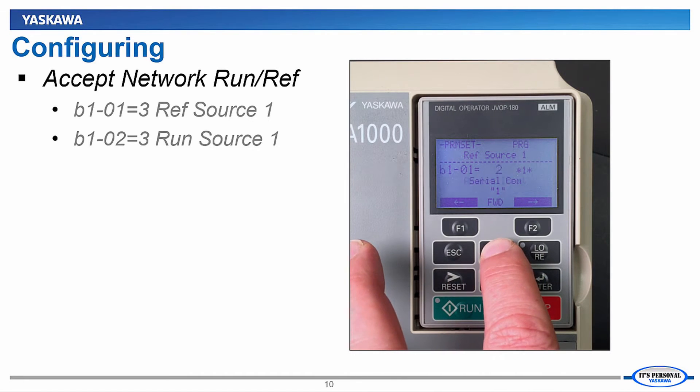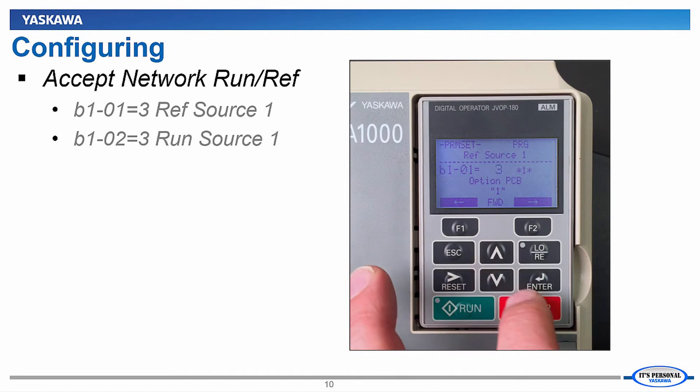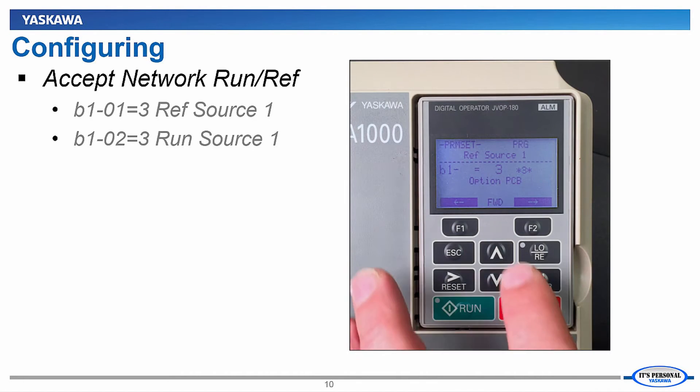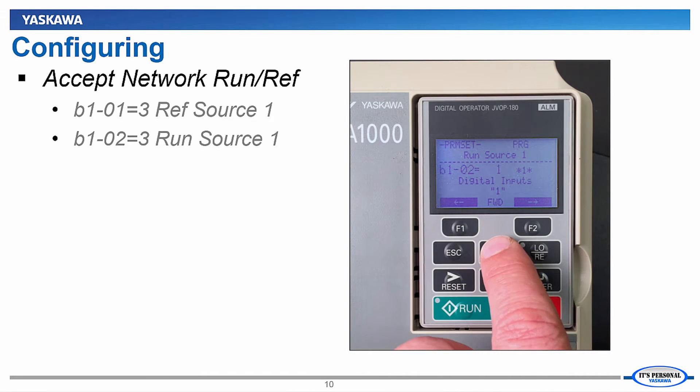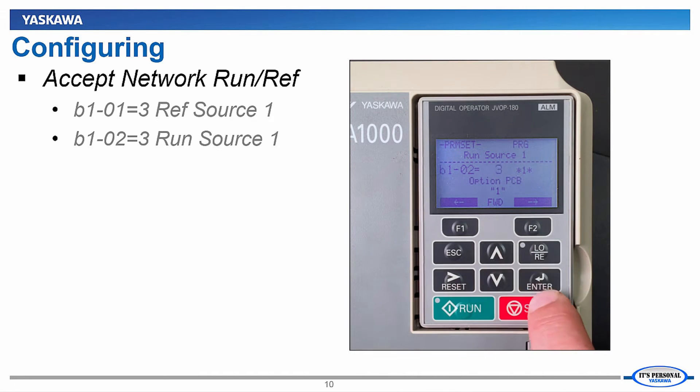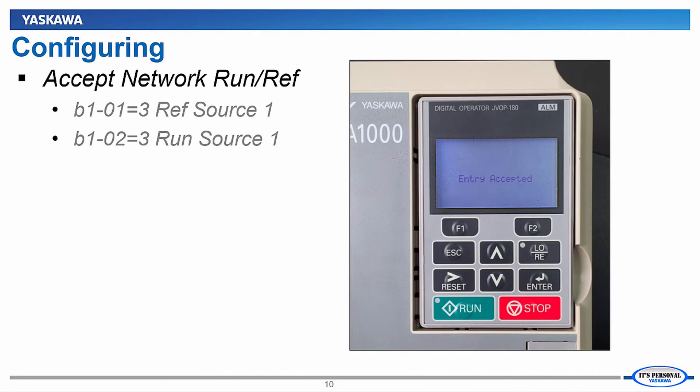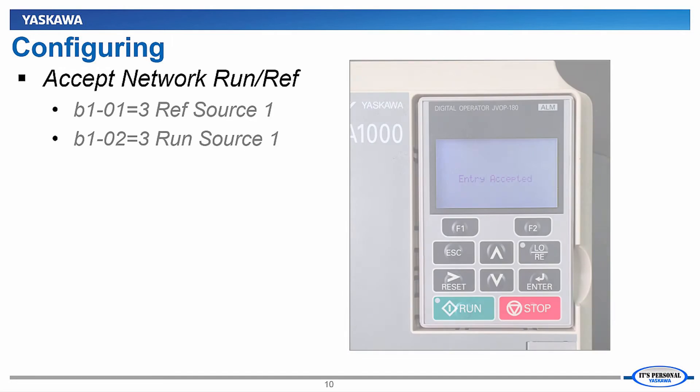To do this, we will need to set parameters B101 and B102 to a setting of 3, which is option printed circuit board. There is no need to cycle power to the VFD after this adjustment.